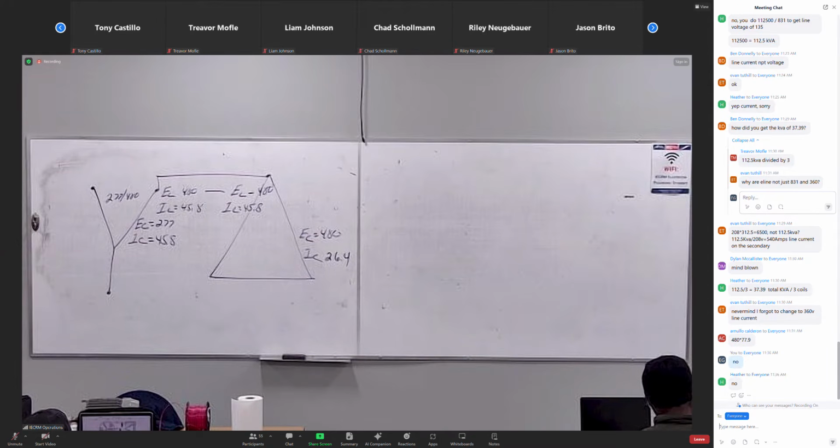So anytime I see 208 3-phase, I no longer think of 208. I think of 360. Does that make sense? Then you can just do a basic Ohm's law calc, right? E divided into KVA, boom. So if you can train yourself to memorize those numbers, 480 volt equals 831 at 3-phase. So it was E for 208? Yes, it's E. Sorry, to get to your question, yes.